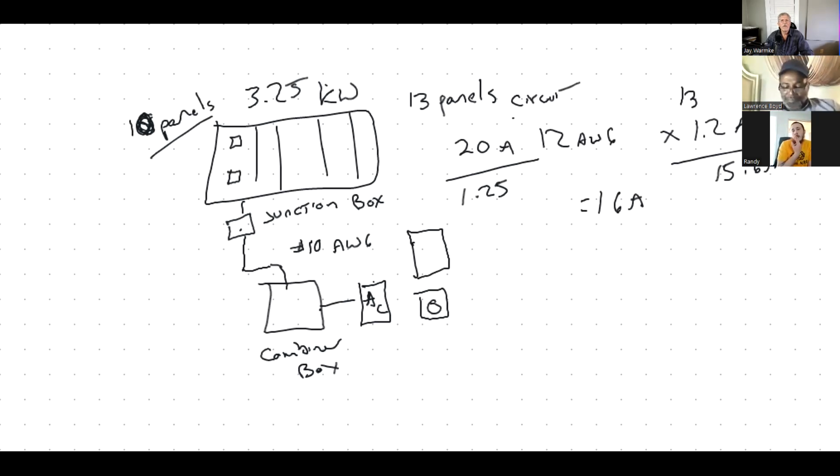So anyway, from our AC disconnect, we're going to go inside the house, and we're going to locate on the breaker that's furthest away from the main, right? Because of the 120% rule. Everyone clear about the 120% rule? So this meter is actually going to be connected to the main here in your service panel.